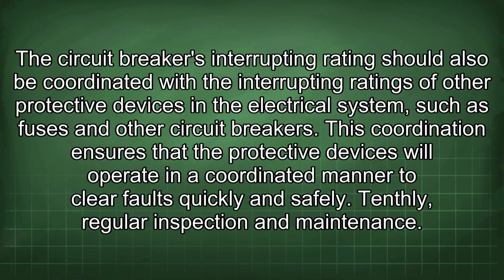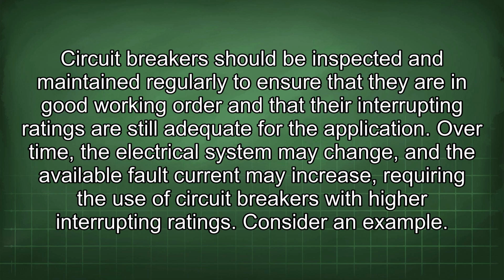Tenthly, regular inspection and maintenance. Circuit breakers should be inspected and maintained regularly to ensure that they are in good working order and that their interrupting ratings are still adequate for the application. Over time, the electrical system may change and the available fault current may increase, requiring the use of circuit breakers with higher interrupting ratings. Consider an example.